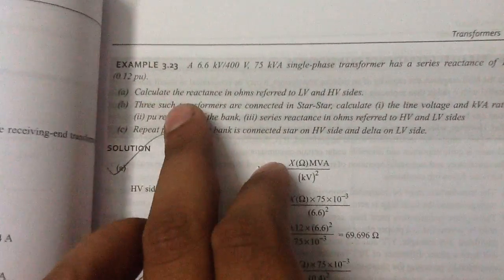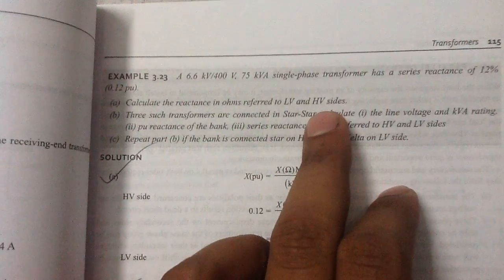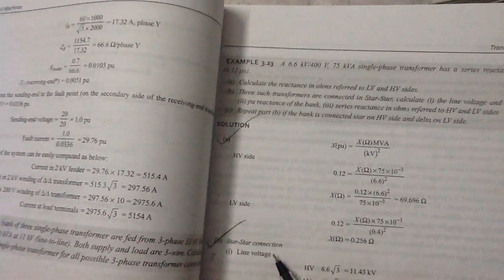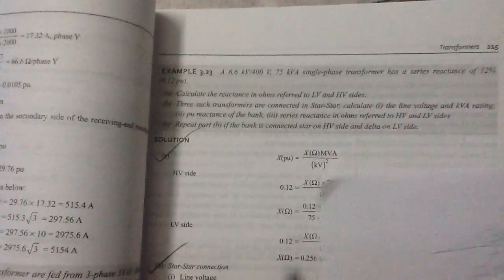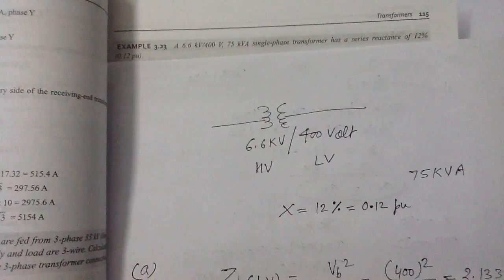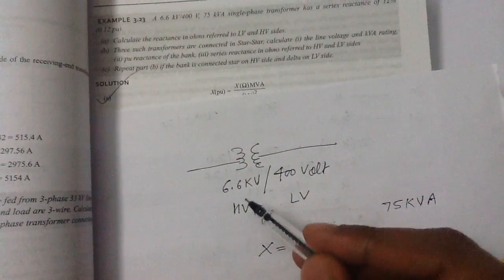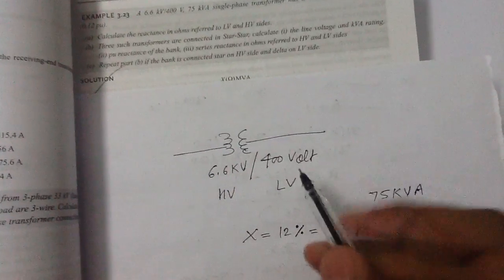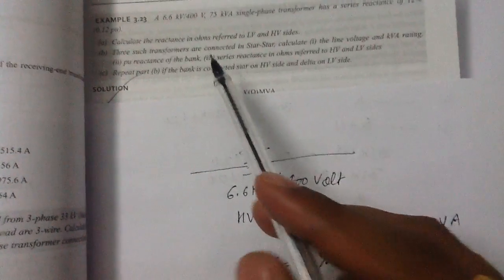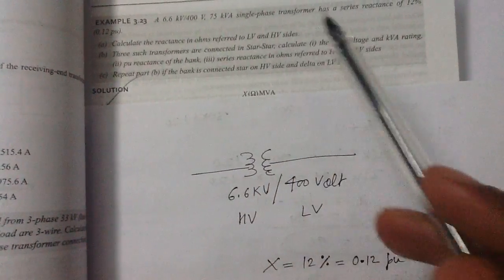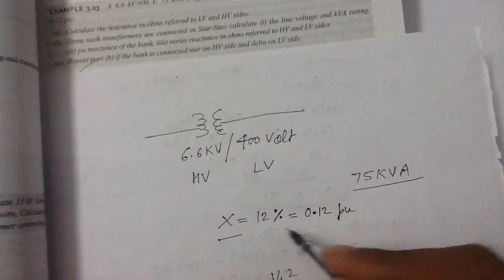Part A asks us to calculate the reactance in ohms referred to the LV side and HV side. In this example (3.23), the HV side voltage rating is 6.6 kilovolt, the LV side voltage rating is 400 volt, the rating is 75 kilovolt-ampere, and the reactance is 12% or 0.12 per unit.